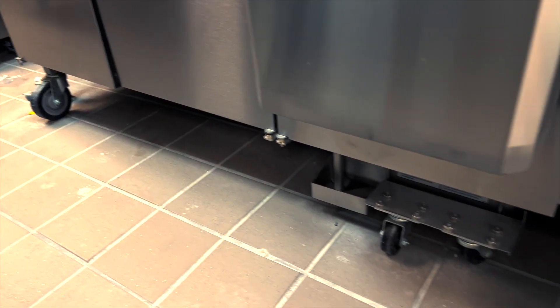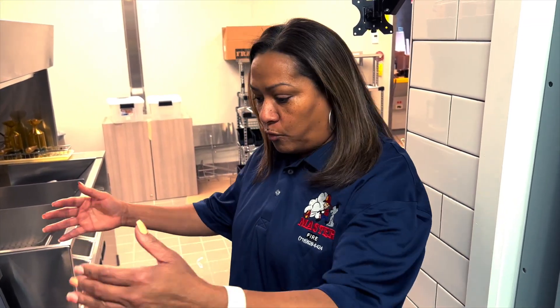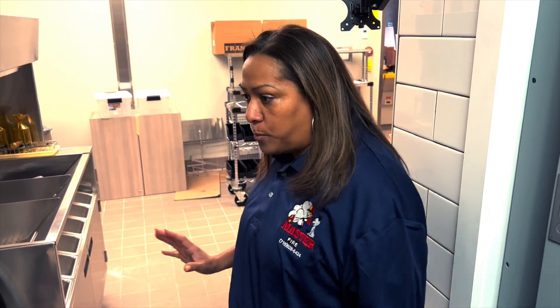Do not move any cooking equipment without letting your fire suppression company know about it. Whenever you remove or move the equipment from the protection of the nozzle, you are tampering with the fire system — you're going to be in violation and the fire department is going to say that you altered the plans. We want you to be very careful when you have cooking equipment that has wheels, as it can come off the position under the spray coverage. The fire department requires you to put a yellow tape, or you can paint a yellow line in front of the wheels when it is in place, so when they come off you can see it and put the equipment back into place.